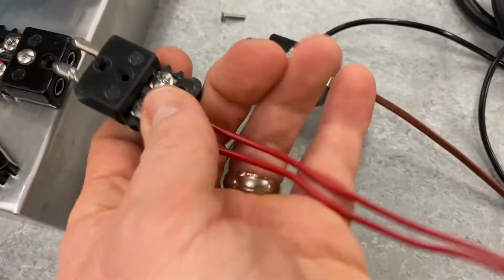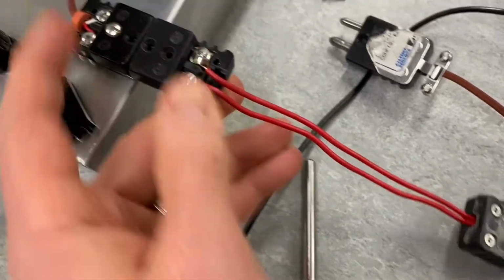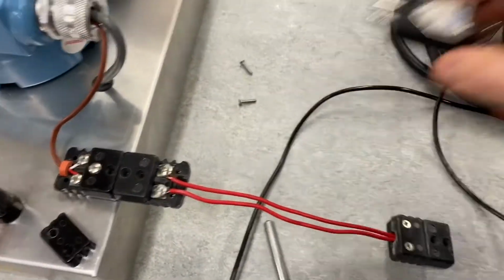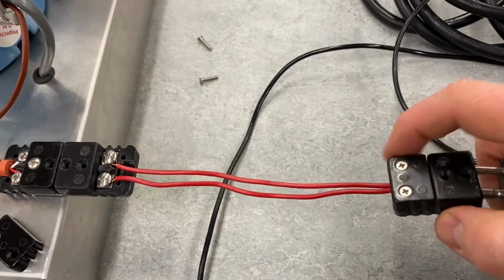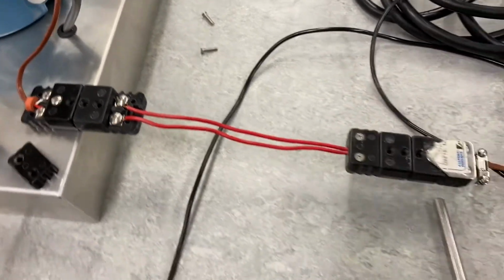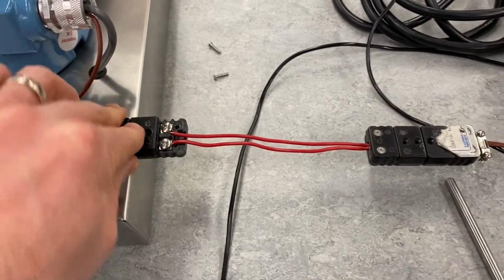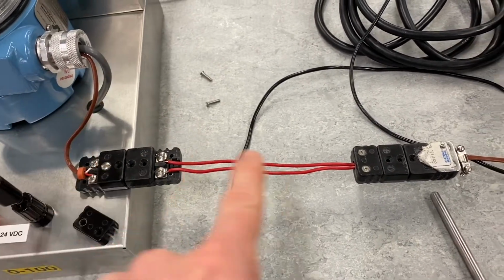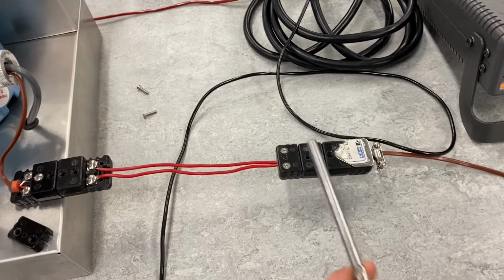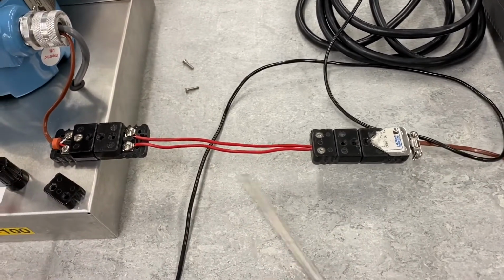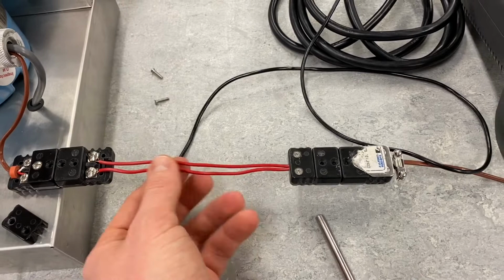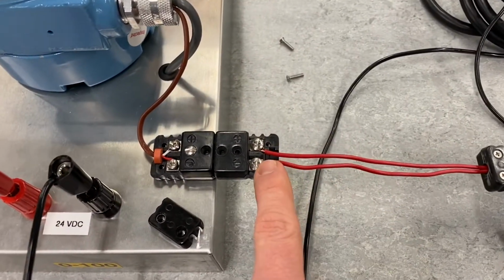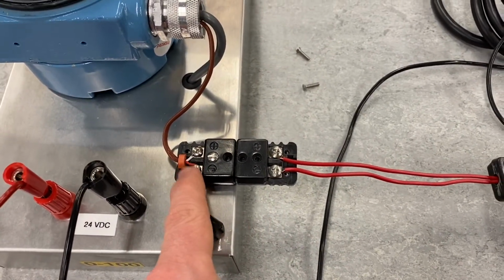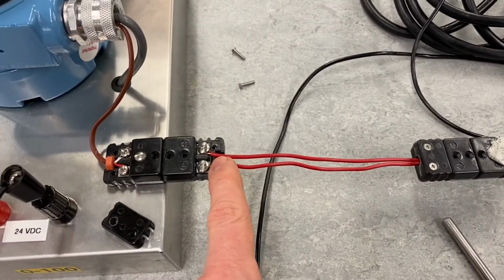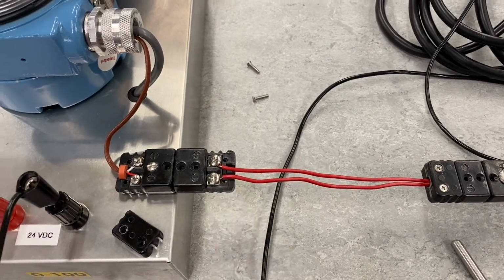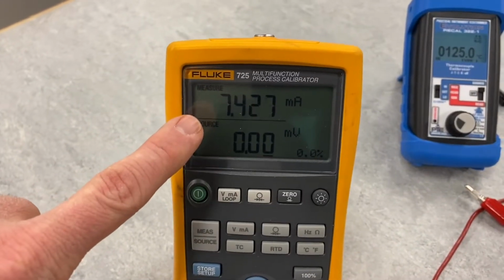So this is going to plug in over here, and then our thermocouple is going to plug in to the end over here. Out in the field, if we need to extend these lines to get to a temperature measurement that's quite a bit further away from the transmitter, a common mistake is to use copper wire. So what we want to see is what happens when we cool this junction versus this junction. We want to make sure we cool this one junction first, then install the copper extension wires and cool this junction and see how it affects our milliamp reading right here.